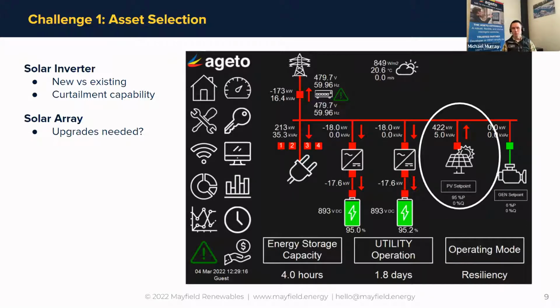But you can't get support on them anymore. You can't integrate with them right now because they don't have the control capabilities that modern inverters do. So on most of those, we are actually just removing them and replacing them with an upgraded modern inverter like SolarEdge, SMA, CPS. Most of the brand name solar inverters in the commercial space have the control capabilities we need to curtail or reduce the output of the solar inverter so it can seamlessly integrate with the microgrid.